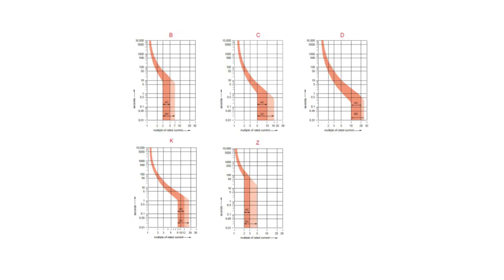As you know, the trip current is the value of current at which the breaker will trip instantaneously. We choose these curves depending on our load type, because some loads have high inrush current at starting which can cause false tripping for the miniature circuit breaker.